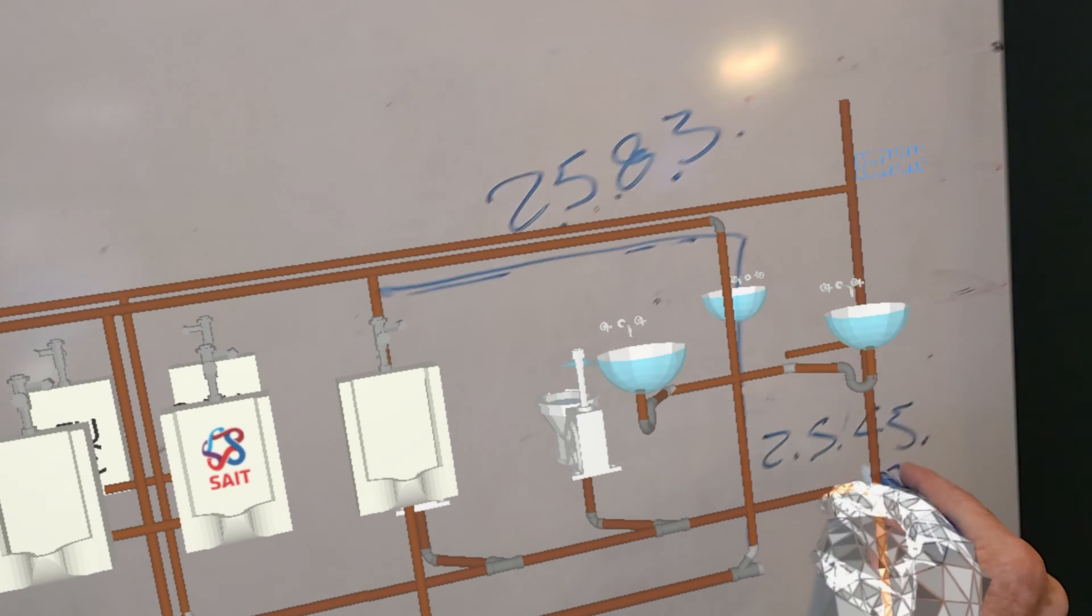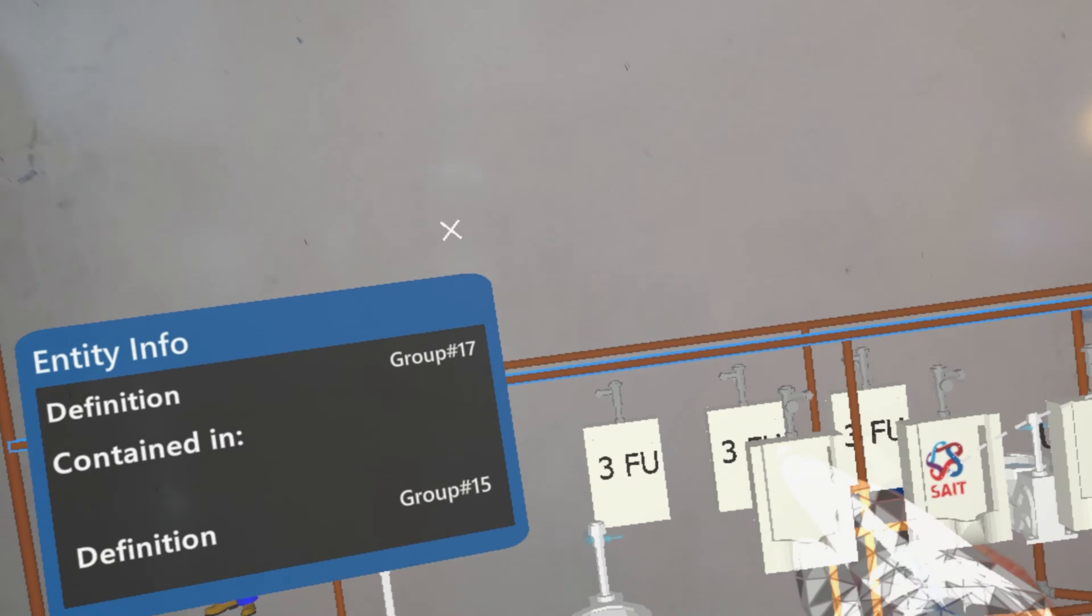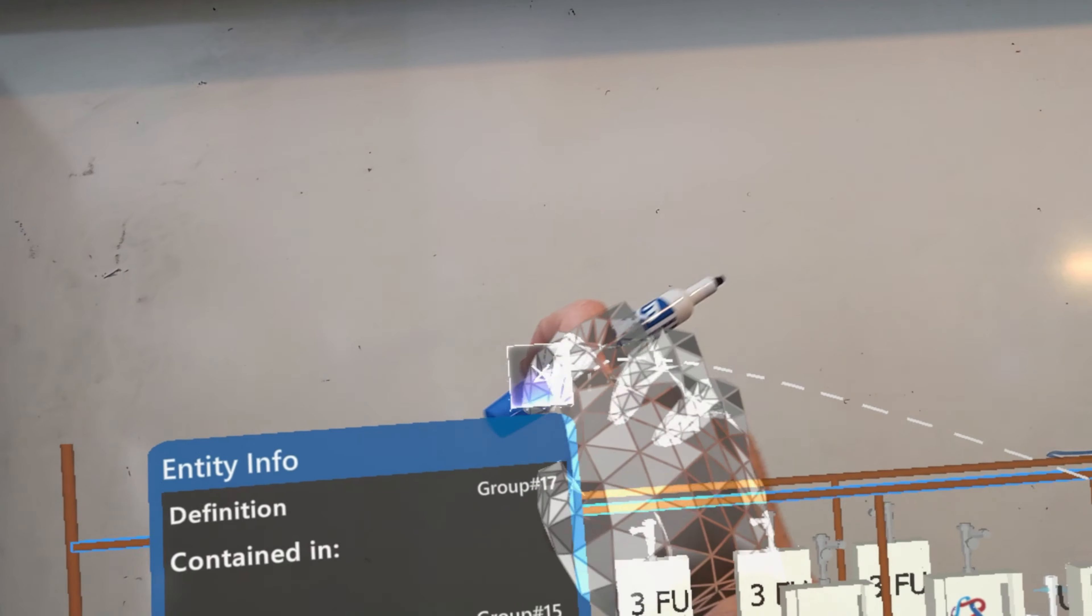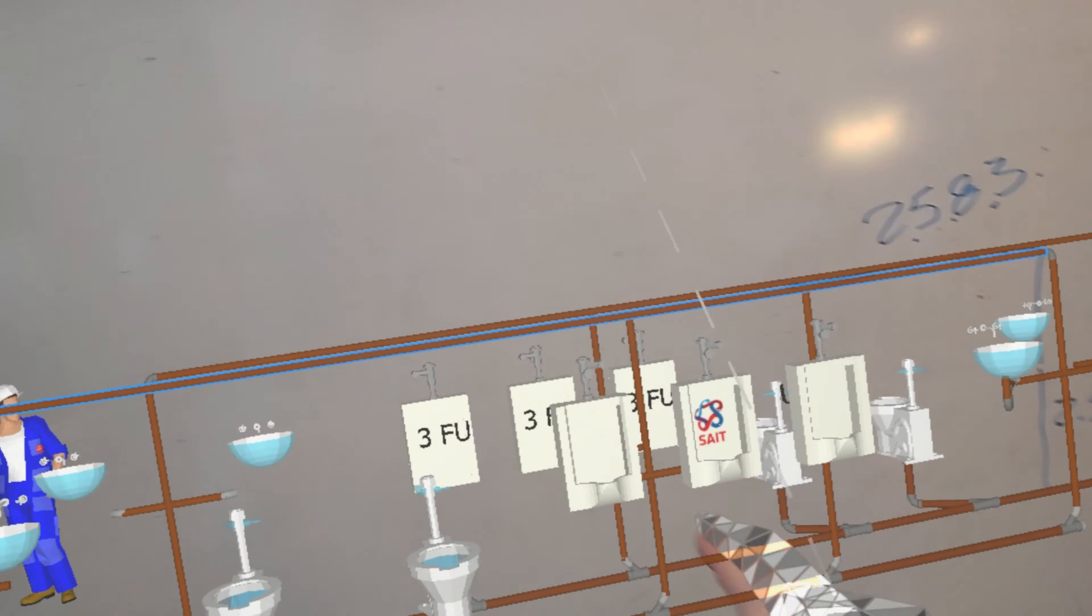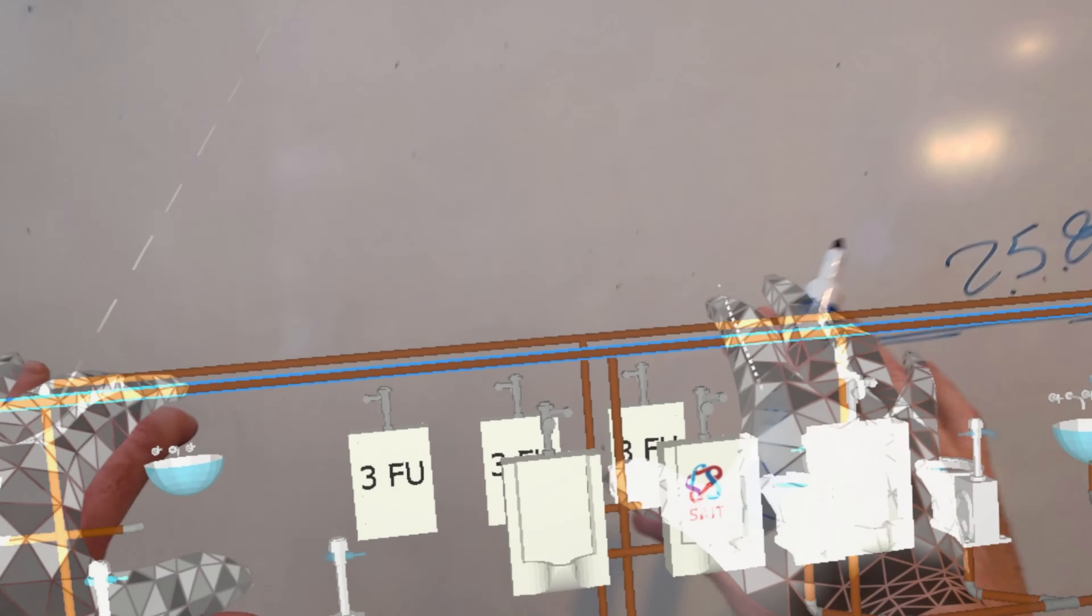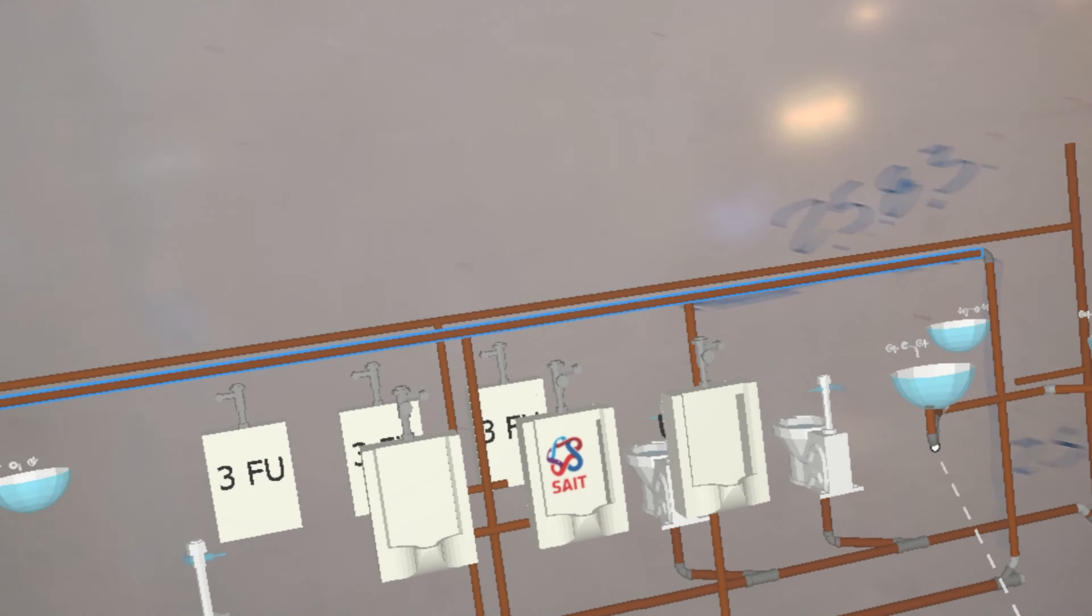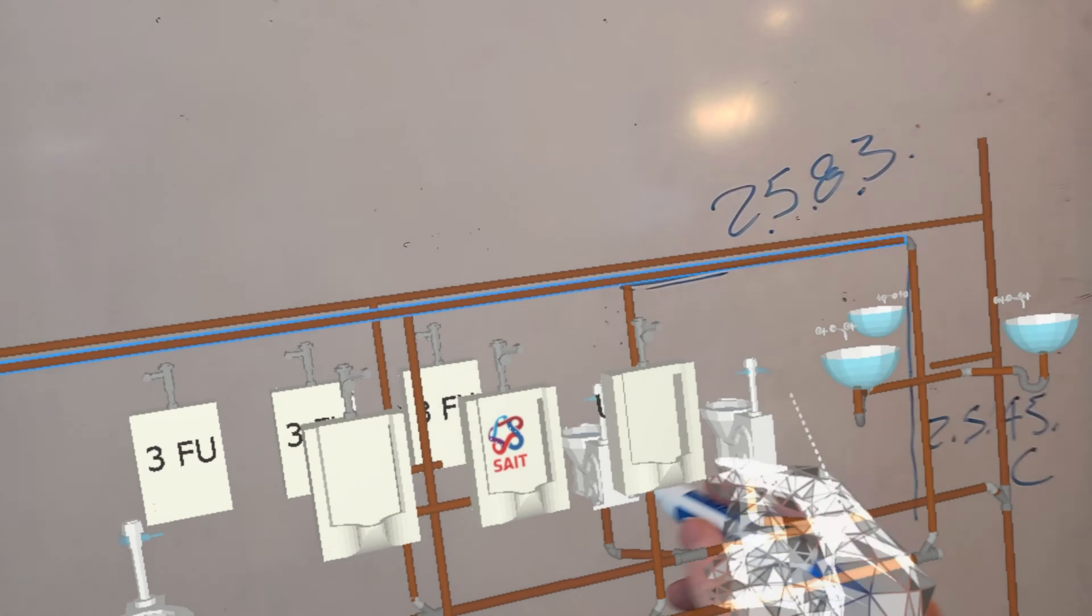And of course you size the wet portion by 2545 subsection C. As it says right here on these urinals, because the bathroom on the other side is identical, it's just the opposite. So these are three fixture unit urinals, as you can find in 2493. You have to figure out which ones are three fixture units.